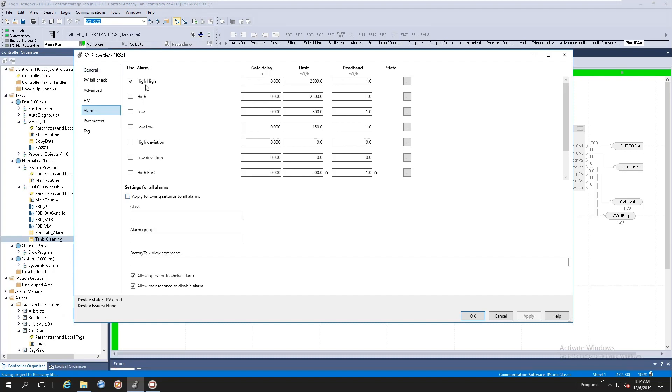So when you instantiate an instruction, you will by default get all these alarms. And when you start doing your alarm rationalization process, you will enable alarms that you require and you'll start doing the configuration at that point in time. So you don't have to go instantiate all your instructions anymore, run it through the alarm builder tool, generate the XML content, and input that into your HMI server. It's now all part of the instruction and it's enabled by default.